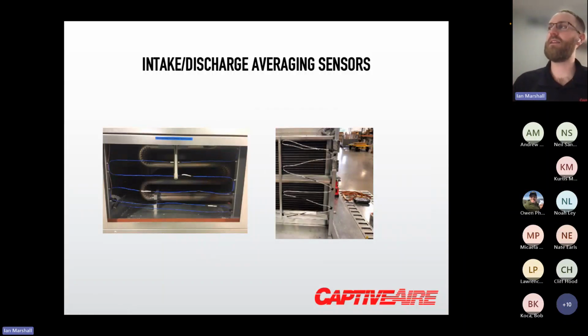We use intake and discharge averaging sensors, particularly on the discharge side. It's really hard to get an accurate discharge temperature reading right off of a heat exchanger on the heating side, because there can be hot spots and non-uniform airflow, so it's hard to get a really exact reading. So we standardize with a factory-mounted discharge averaging sensor, which has proven to be pretty accurate and doesn't require any downstream field-mounted temp sensors, which is convenient. Just one less thing to get missed during install. We also do that on the intake side, for if we're doing partial recirc, just to give a more uniform intake reading.